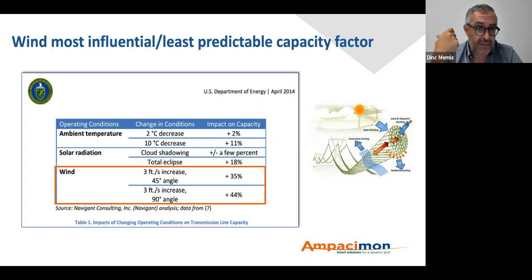The reason we think the sensor is really critical to measure the wind impact is that we have observed different weather station impacts on the wind. We found that many times they are not in the right location or at the right height, or the anemometer is not even measuring lower wind speeds, like below 2 meters per second. That is why I want to highlight that in sensor-based dynamic line rating, wind is the most influential and probably the least predictable capacity factor, and our sensor provides lots of insight into what we can gain from it.